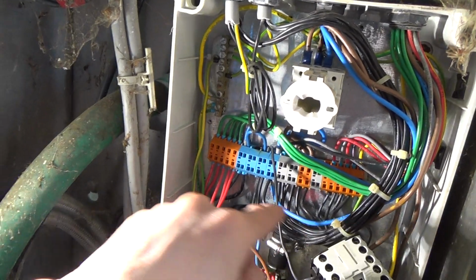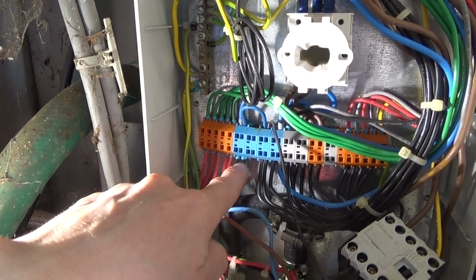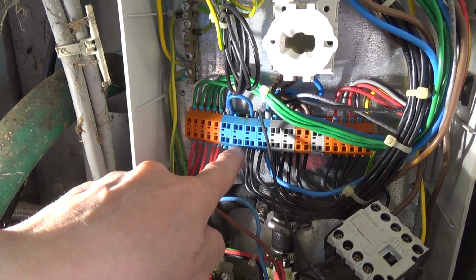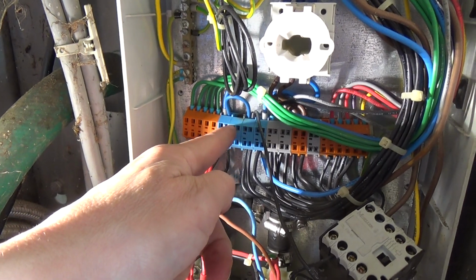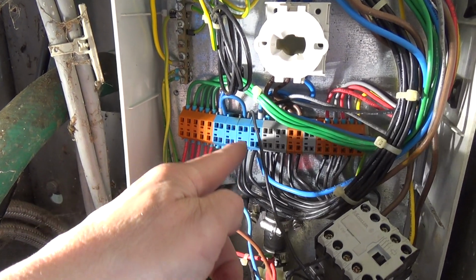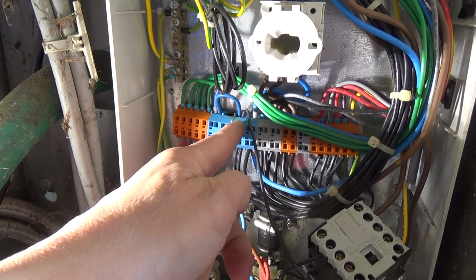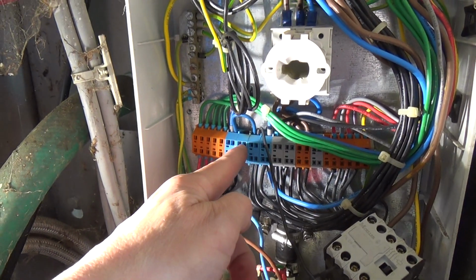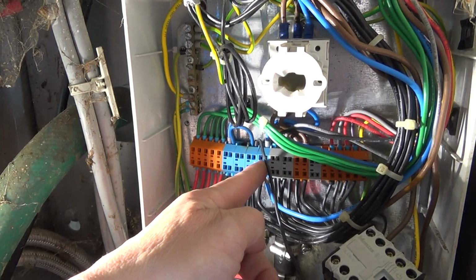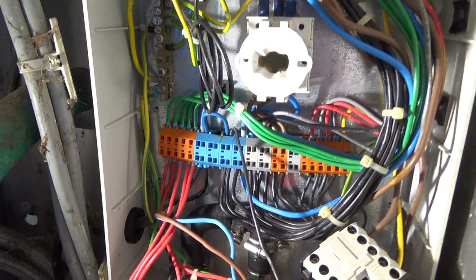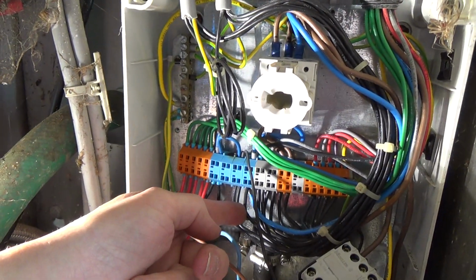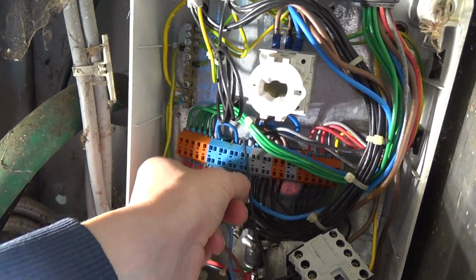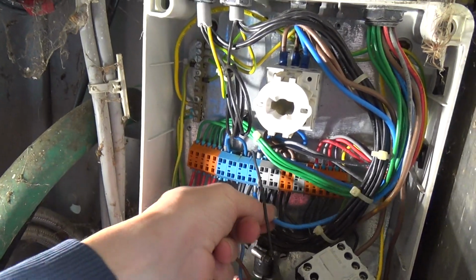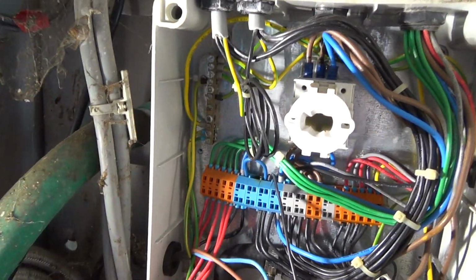This wire may have been in here previously. And there was probably a little loop that went into there and a little loop that went into there and then into here, so we'd have had switch neutral, switch neutral, switch neutral, incoming neutral. Now somebody's put a switch neutral in the incoming neutral probably, this one here, because that's burnt out at the top.